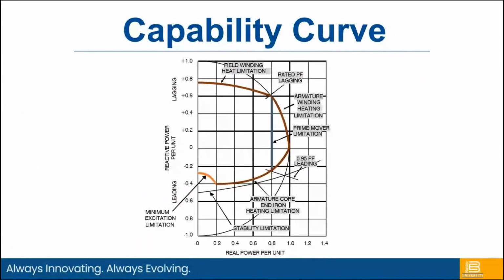Going back to my presentation real quick, what we're trying to do with our limiters is keep the generator within this capability curve. So your generator should have a published capability curve, the D curve, as it's commonly referred to. This upper line here is the overexcitation limit. We need to set the overexcitation limiter within that so that you don't reach that field winding heat limitation of your machine. And that's the main field.